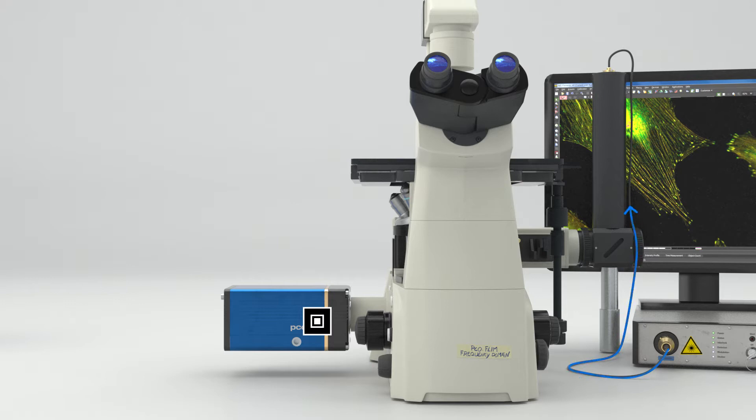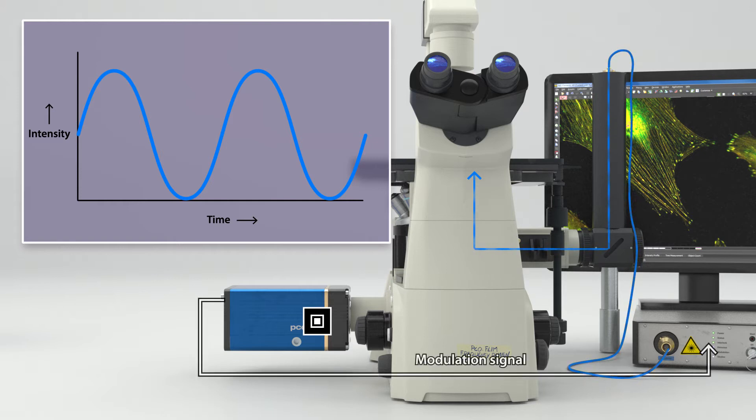In this frequency domain approach, the intensity of the excitation light is continuously modulated using sine or square waves. The modulation source is the camera, which provides modulation frequencies ranging from 5 kHz up to 40 MHz as well as the signal for dark gating.